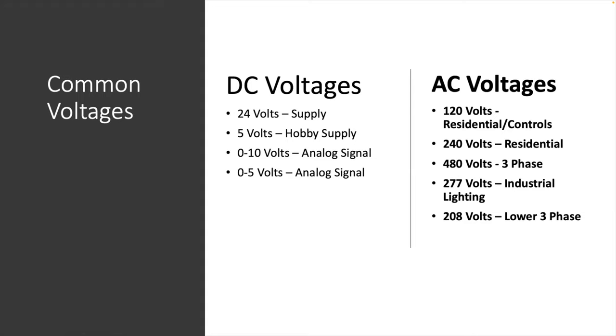As far as AC voltages in industry: 120 volts can be used both in residential and in motor controls, as well as some office buildings. 240 volts is generally used in residential for things like a water heater or a dryer. 480 volts is three-phase, so a lot of times you'll have Y and Delta 480-volt systems in industry. 277 volts you'll see a lot of times in industrial lighting — it's actually one phase off of 480-volt three-phase. 208 volts is the lower three-phase, and one phase off of a 208-volt system is actually 120 volts. In fluid power systems, we use these voltages for motor controls to control things like proportional valves, directional control valves, or other types of solenoids to drive a fluid power system, whether that be hydraulics or pneumatics.